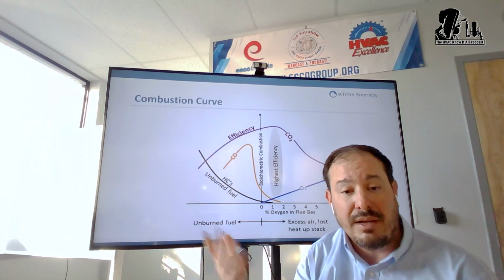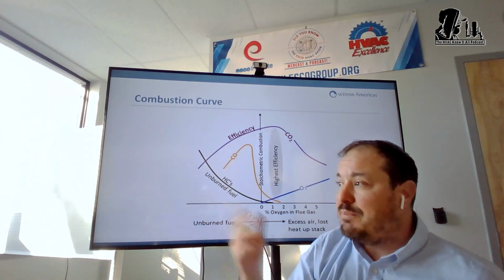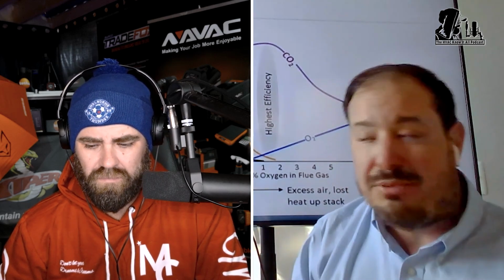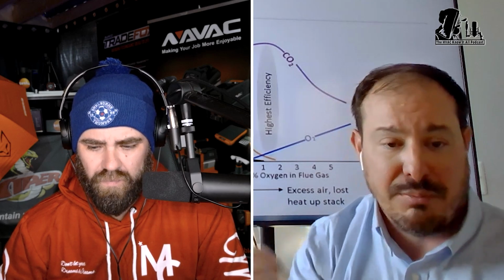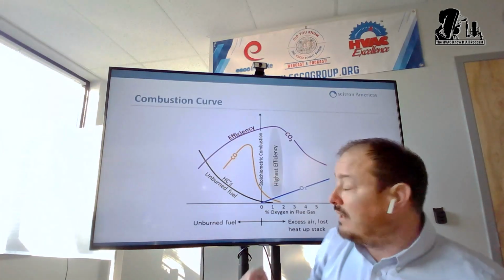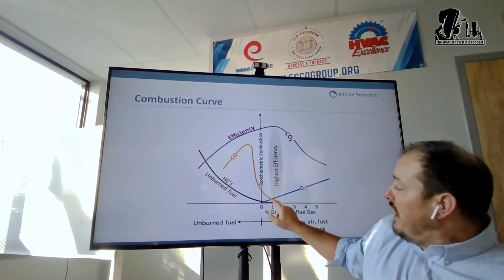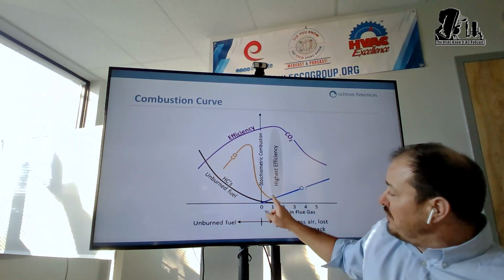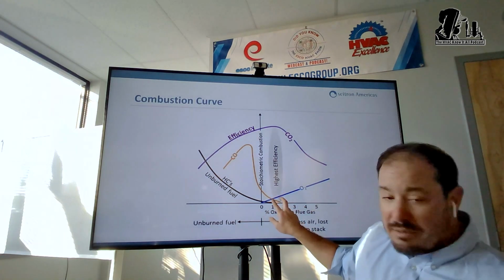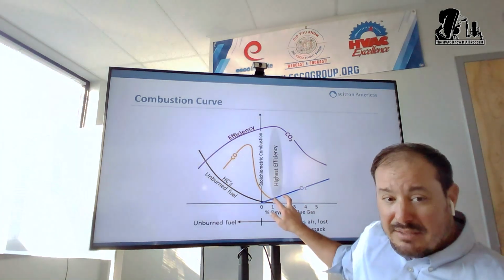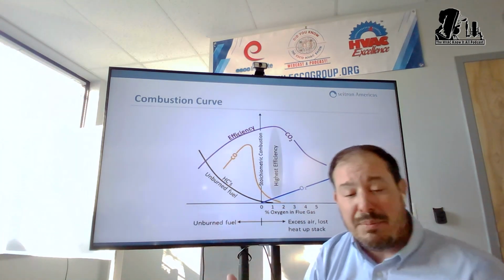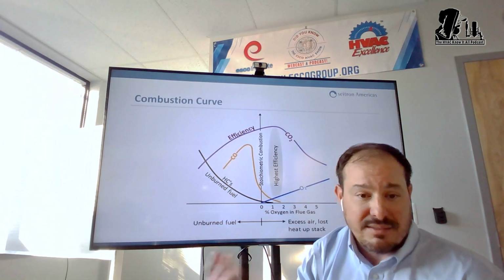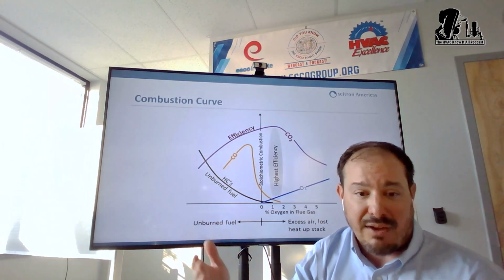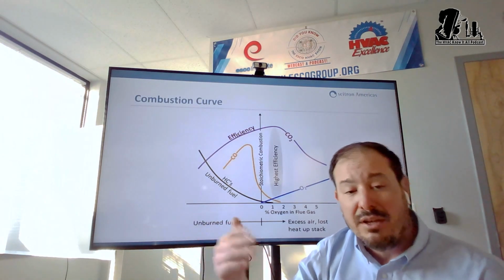So to give you an example, right? On let's say a 90% boiler, if I look at a new condensing boiler, my oxygen should be between, let's say, 5 and 7%, to give you an example. Some manufacturers are a little bit different, but let's say it's 5 to 7%. If you see the curve or the highest efficiency range, I know I should be between this number and this number. Combustion is always a range. Am I going to be in this good range? CO, typically 100 ppm or less is a good range, but some manufacturers on high fire will give you 150, 175, whatever the case may be.